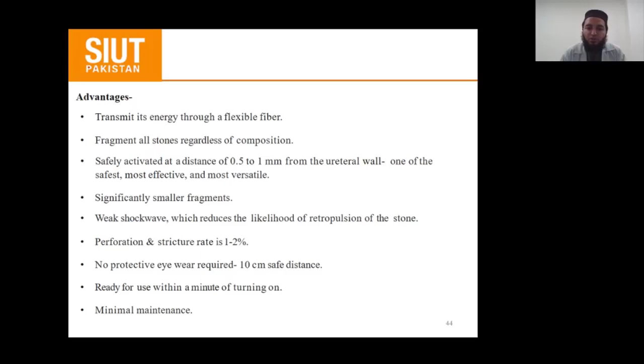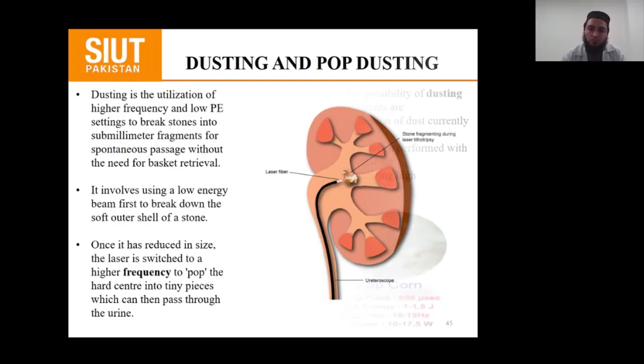Dusting and popdusting. Dusting is the utilization of higher frequency and low power energy settings to break stones into sub-millimeter fragments for spontaneous passage without the need for basket retrieval. It involves using a low energy beam first to break down the soft outer shell of the stone. Once it has reduced in size, the laser is switched to a higher frequency to pop the hard center into tiny pieces, which can then pass through the urine. So this diagram, which shows dusting, fragmentation, and popcorn effect, was once, you can remember, shared in the infographics group.